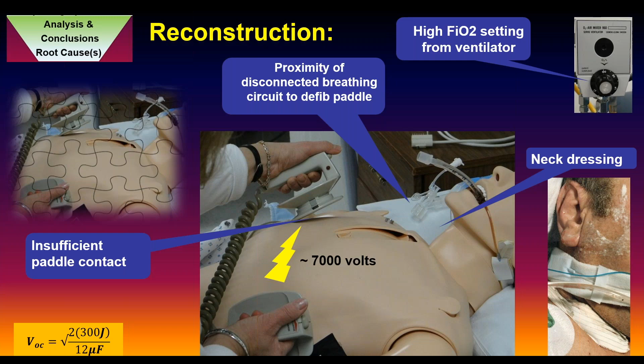Also, the patient had a ventilator, endotrach tube in. They disconnect the ventilator and they just put the hose next to his neck. But see FiO2 on the blender, close to 100% O2, flooding the head and neck with pure oxygen. He had a Swan line in, big 4x4 gauze on his neck. They went to discharge, incomplete paddle contact, an arc. So that's what I effectively put back together. And the first thing they want to do is blame the nurse, but this is classic James Reason Swiss cheese. It's just the alignment of these stars here that created the problem.